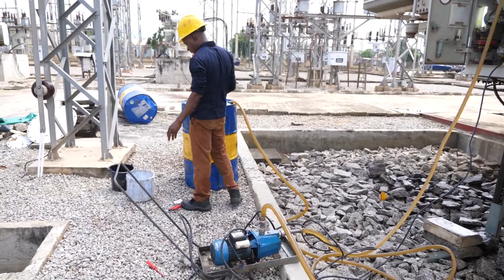So that's why we make sure once in a while we come, we open up the diverter switch, we remove that carbonized oil, we flush it, wash it properly with clean oil, then finally we introduce new transformer oil, and our transformer takes off as a new one.